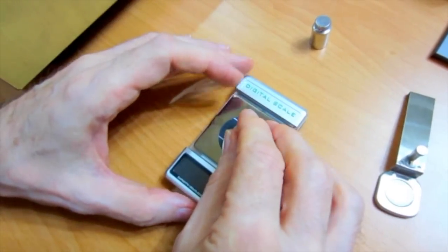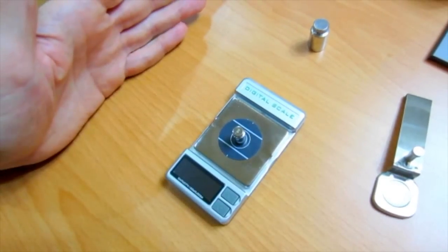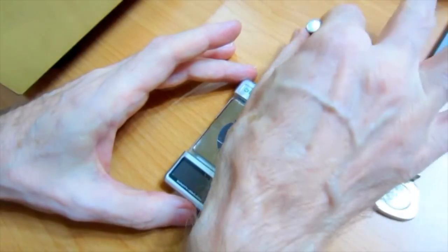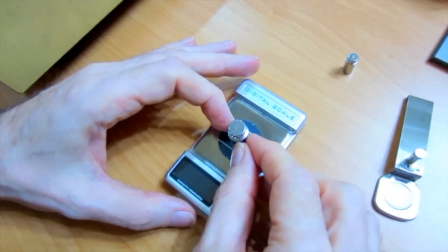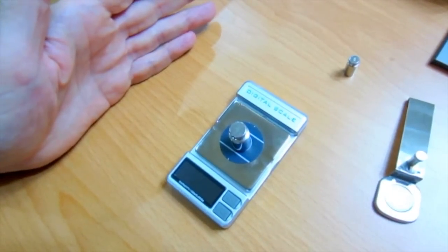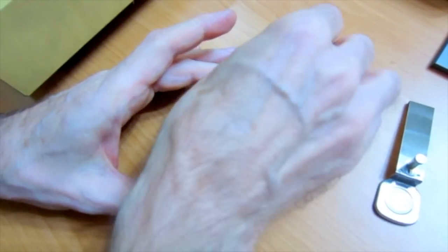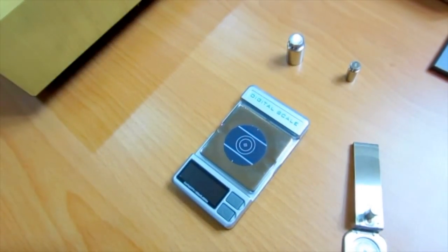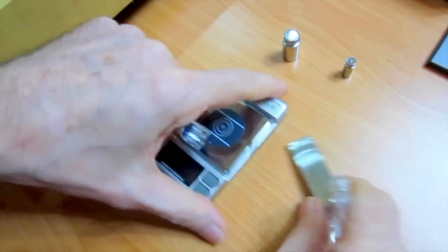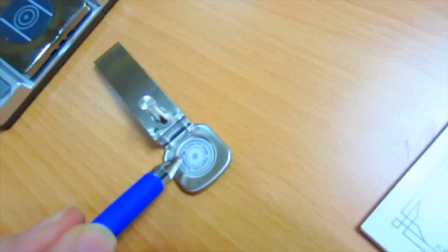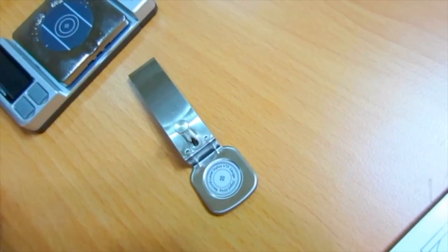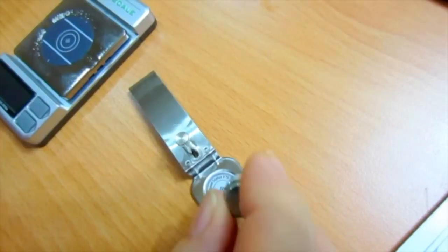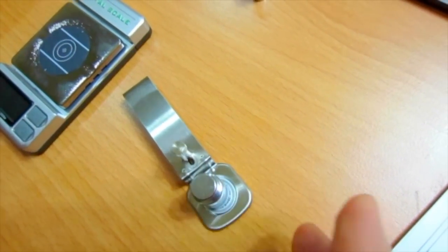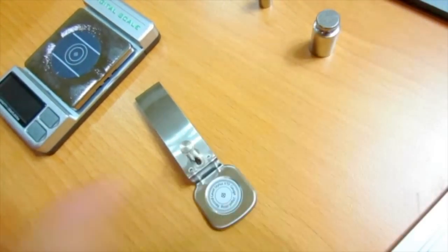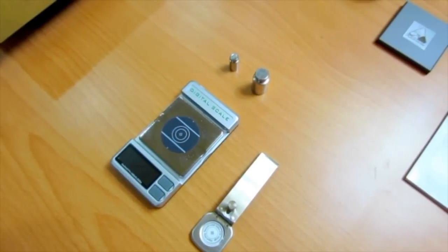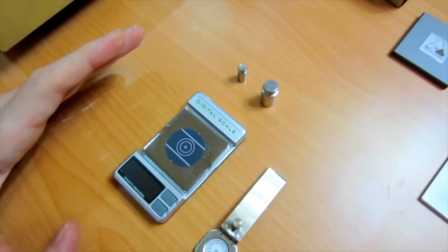The inner circle is for calibration with a 5 gram mass, just so you can better center it. The outer circle is a centering point for the 20 gram mass. Alright, you'll notice the same circles on the polymer pad at the end of the extension arm. The inner one for 5 gram mass, the outer one is to center the 20 gram mass when you go through the calibration. Alright. Okay, let's go through a typical calibration.